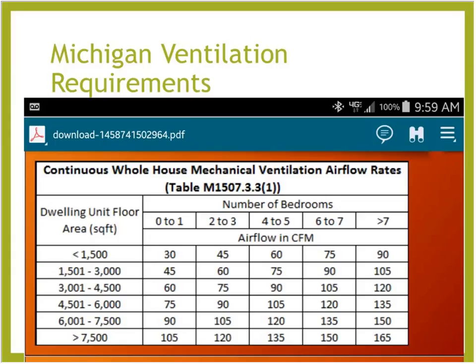Yeah, we would do that from the exterior of the home with the flow hood. But I will tell you that typically what is happening is we're being provided with calculations based on optimal performance. So if you've got a 25 Pascal pressure on the duct system, and that has a 4-inch fresh air intake, that's typically somewhere between 35 and 40 CFM of fresh air being supplied. But that doesn't take into consideration the install, that's just under optimal performance, and it's about 67 CFM under a 6-inch duct. But that's all theory. It's not in real world practice.